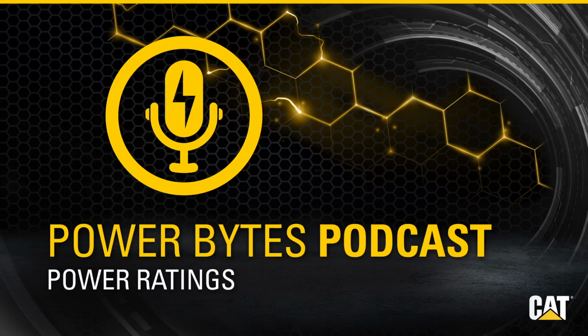So for an example, if you had a generator that had run for 490 hours over the course of a year, and now you've got a large outage that has just occurred, the generator is not going to automatically shut down at 500 hours. It's going to continue to operate and will continue to support you through the duration of that outage. Now, we would recommend that you work with your dealer to schedule maintenance at the next most convenient time so that you're checking to make sure that it's still operating and will be ready for you in your next outage. But overall, the CAT product is going to continue to support our customers as it goes through those outages.